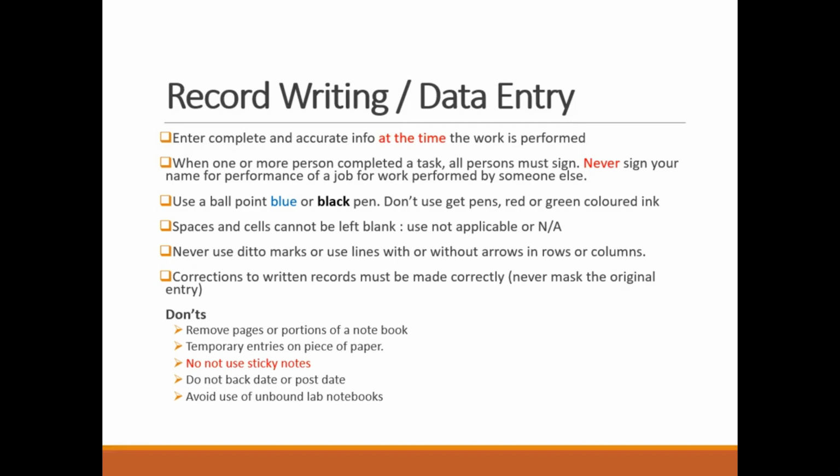Corrections to written records must be made correctly. Never mask or obscure the original entry. Don'ts include remove pages or portions out of a notebook, temporary entries on a piece of paper. So we never want to see sticky notes lying around the laboratory or loose pieces of paper with data entry on it. Sticky notes are a huge no-no for audit, so I've highlighted that one in red.